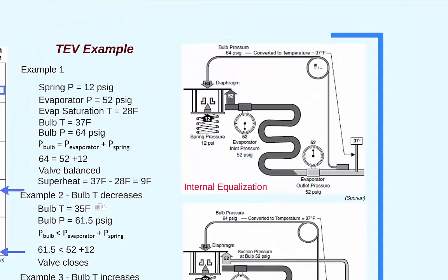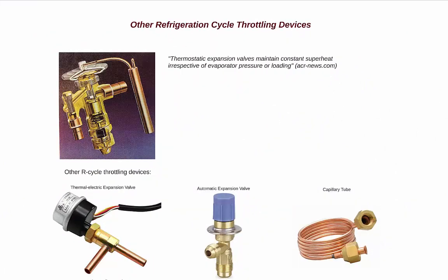As an example, the schematic on the bottom shows the evaporator inlet has a pressure of 58 psi, but the outlet operates at 52 psi. In this case, the evaporator pressure exerted on the valve diaphragm is taken from the evaporator outlet. This is required in order to accurately control superheat without dependence on the fluctuating evaporator pressure drop.